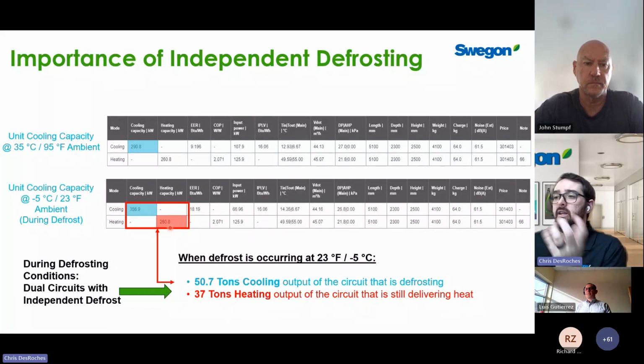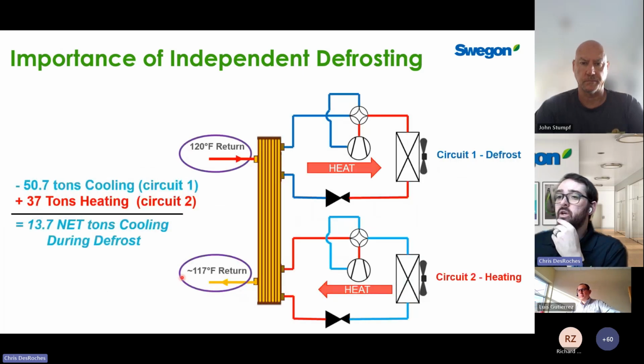It's not providing any heating. It's not providing any cooling. That's in fact not true. It really depends on the conditions, because we also need to consider that as it gets colder outside, our heating capacity is decreasing as it gets colder. So at this condition of 23F, where one circuit's providing cooling and the other's providing heating, we actually end up being slightly cooling dominant, providing about 14 net tons of cooling capacity to our building.